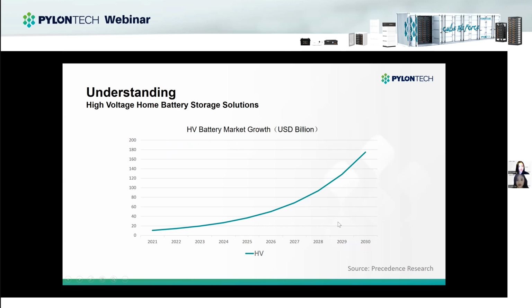So according to families' requirements, more and more high power inverters are on the market, such as 15 kilowatt and 20 kilowatt. And if you use low voltage batteries, you may use 4 to 6 battery modules, then the current would be very big.